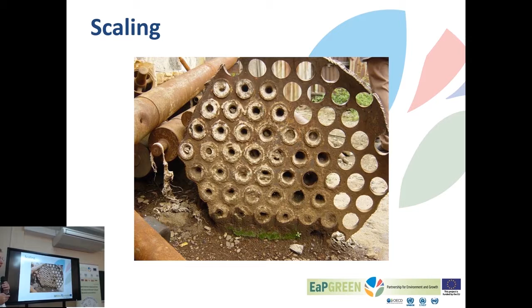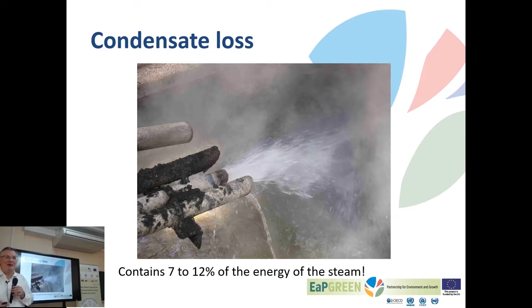Our topic was condensate return in the dairy when you generate steam. After the steam has heated something, hot water in the pasteurizer, condensate will form, which should be returned to the boiler. Why? Because the condensate still, depending on the pressure level, contains 7 to 12% of the heat it took to provide this steam. So by dumping the condensate, we are sending away 10% of the energy which we put into the boiler. And how much does it cost to build a return pipe to the boiler house to collect the condensate and to reuse it as feed water? Usually these measures pay back in 4 months, 6 months, for sure less than a year, because we are all paying more or less very similar energy prices. So this logic works globally.